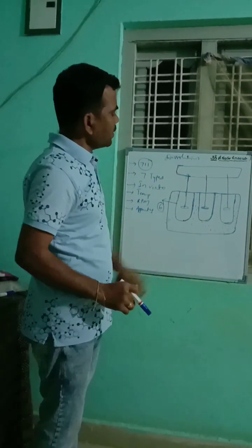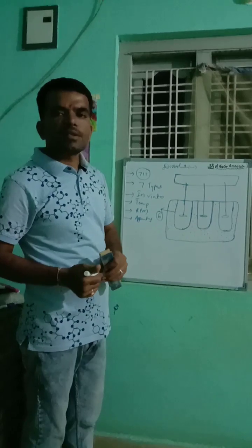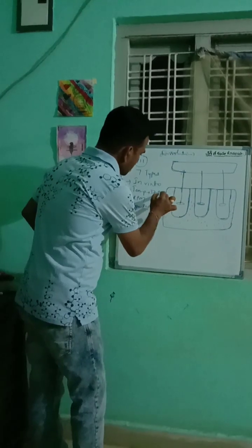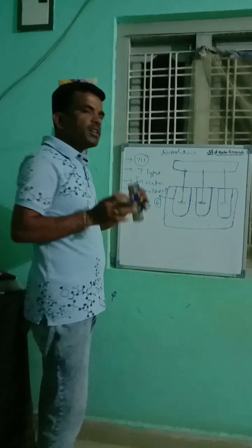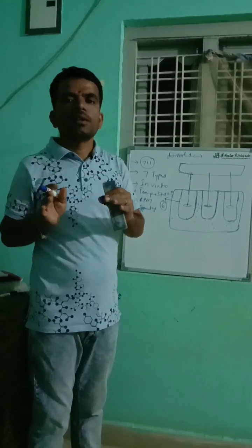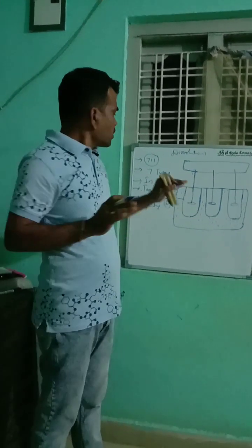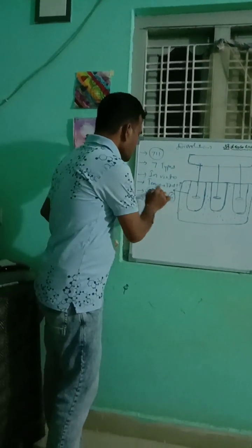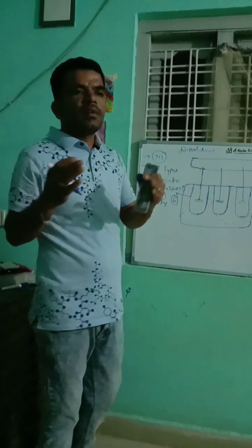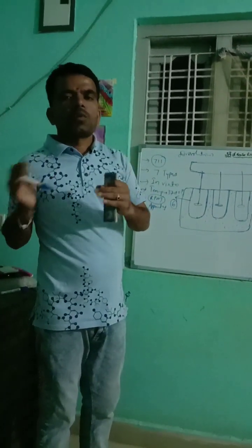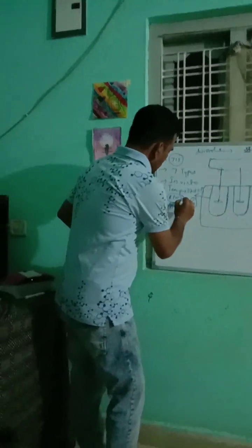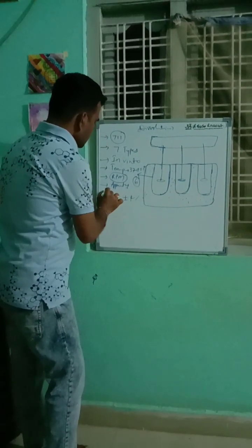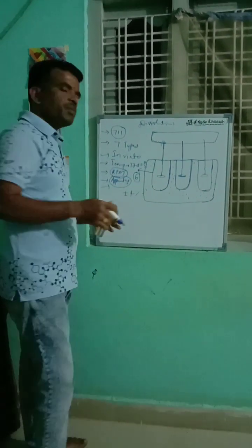Temperature: we have to maintain 37 during the analysis. The tolerance limit for the temperature is 37 plus or minus 0.5 degrees. You can tolerate the temperature only up to plus or minus 0.5 degrees. You should maintain 37 degrees during the analysis. And RPM also depends on the drug. Different drugs have different RPM for different pharmacopoeias. You can tolerate the RPM plus or minus 4%. And apparatus also depends on the pharmacopoeia and the drug.